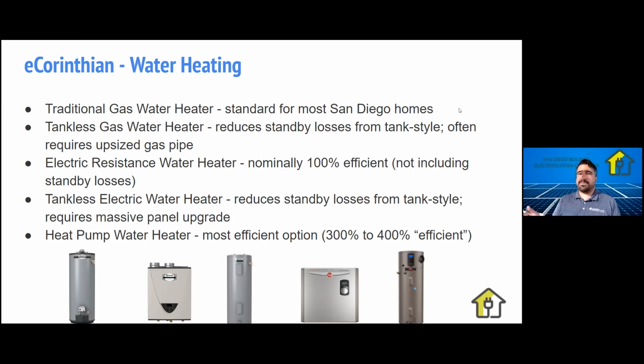There are a few different electric options. There's a standard electric tanked, or electric resistance, water heater. This is nominally 100% efficient — all the electricity burned goes toward heating the water. That doesn't include standby losses, which you can eliminate by going tankless electric, but these are pretty beefy units. They require a lot of electricity at once to instantaneously heat water on demand, so in most cases it's going to require a panel upgrade.